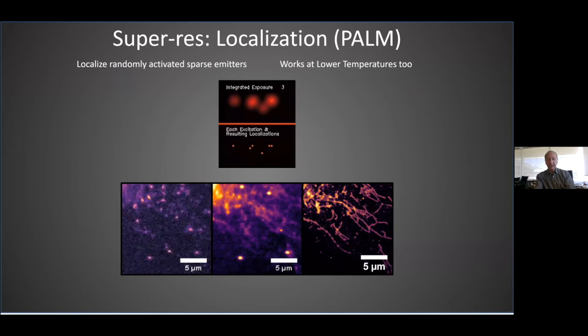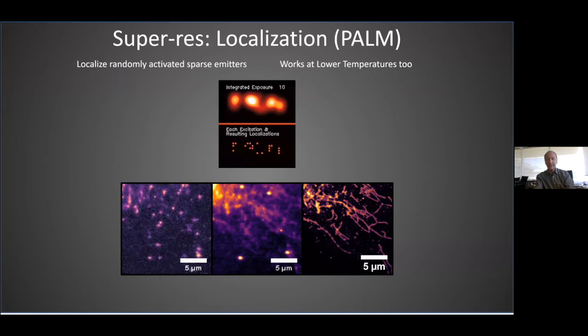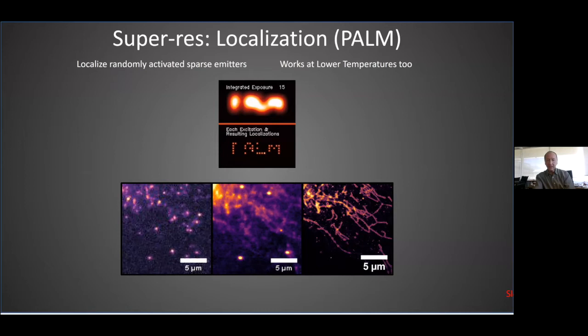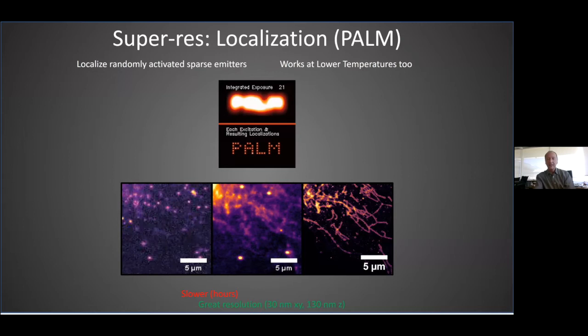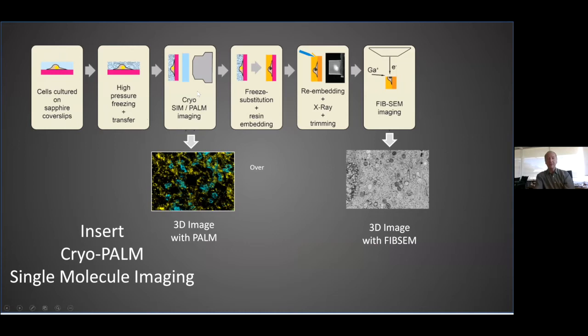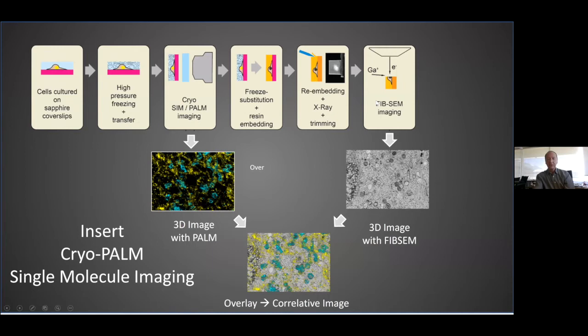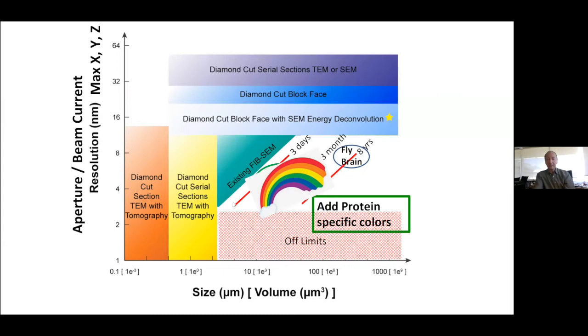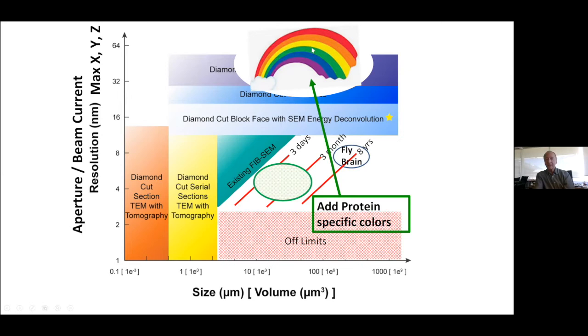Now, one thing as we explore different fluorophores, we learned that, oh gosh, indeed, some of these fluorophores really do blink very nicely, which of course brings up the idea of doing localization microscopy. It's slow. We sometimes take, as in the old days, maybe a day to acquire such a dataset. But the nice thing, it's a technique that inserts into this process flow, but literally does not compromise the quality of the FIB-SEM image at the end. Since we just take it out, keep it cold, image it cold, keep it cold, put it through the rest of the process. And now the two images can be overlaid to give the correlative image. So now we've added another dimension of color onto this area. Actually, maybe it was presenting that a little bit optimistically. The resolution of the color is not as good as the EM, but sort of sits up here. But you do have this resolution data underneath available.